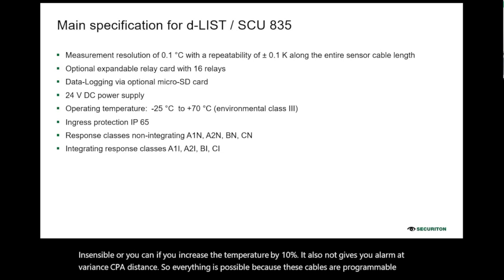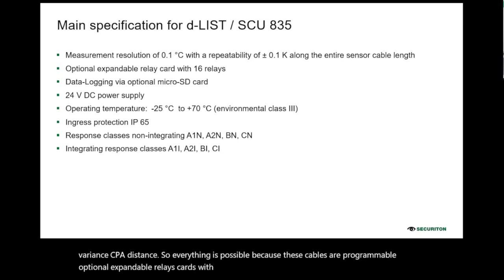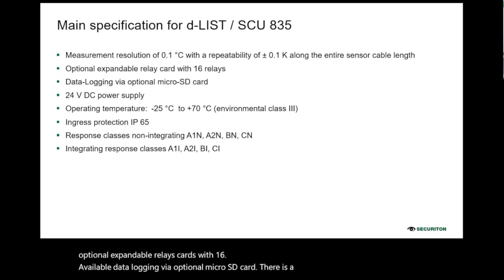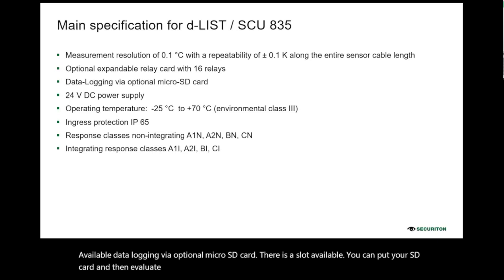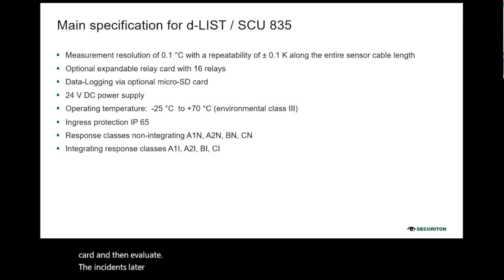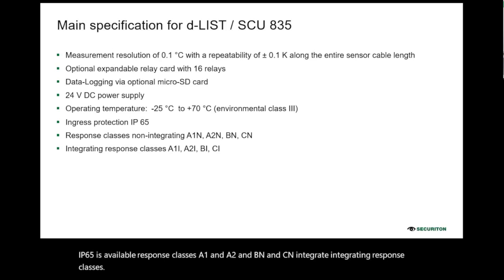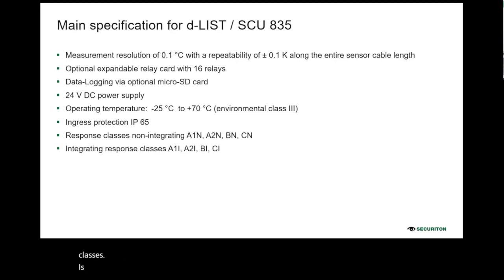Optional expandable relay cards with 16 relays are available. Data logging is via an optional micro SD card. There is a slot available. You can put in your SD card and then evaluate the incidents later on. You require a 24-volt DC power supply. Operating temperature is -25 to +70 degrees centigrade. IP65 is available. Response classes A1N, A2N, BN, and CN. Integrating response classes are also supported with this.